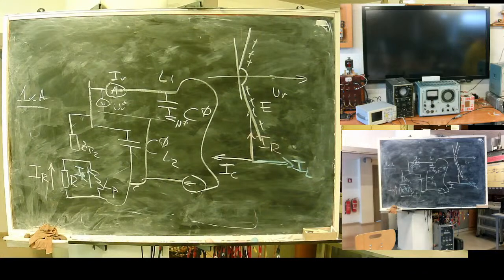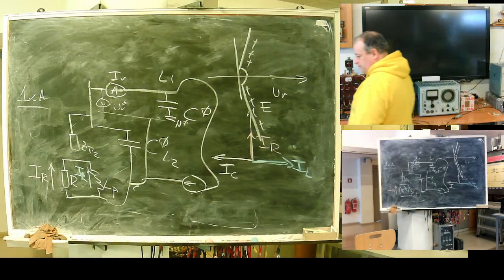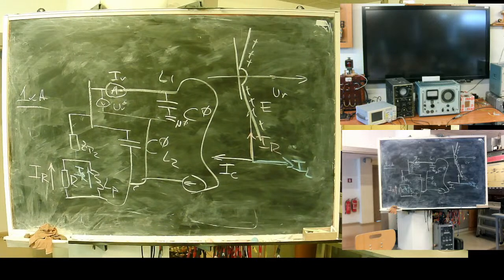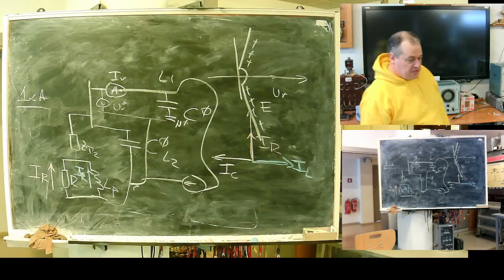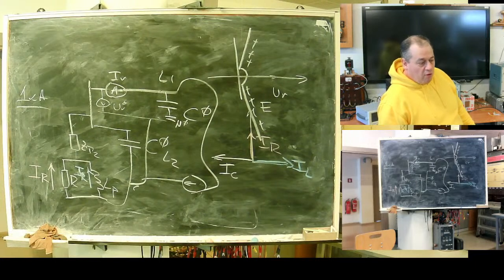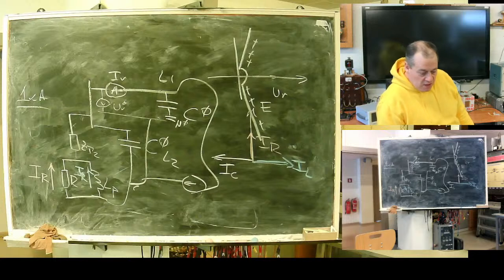If your neutral forming transformer is damaged or disconnected or something happened, if your resistor is not healthy, your protection will not work. You will be in compensated neutral mode. It is important to periodically check this whole compensation branch for operation. It should be closed manually for a short time and the current checked. You need to be sure what current through the resistor emerges.